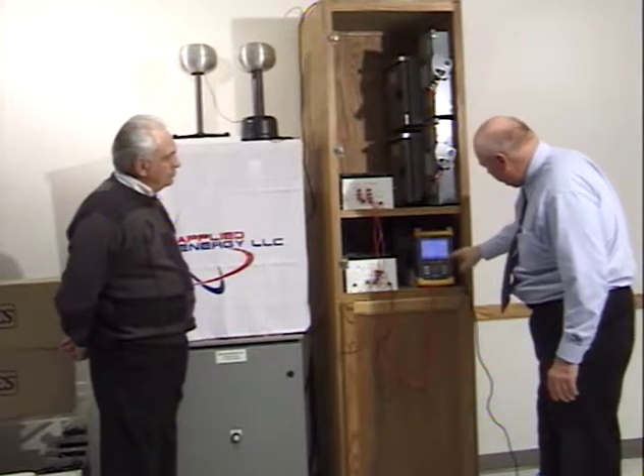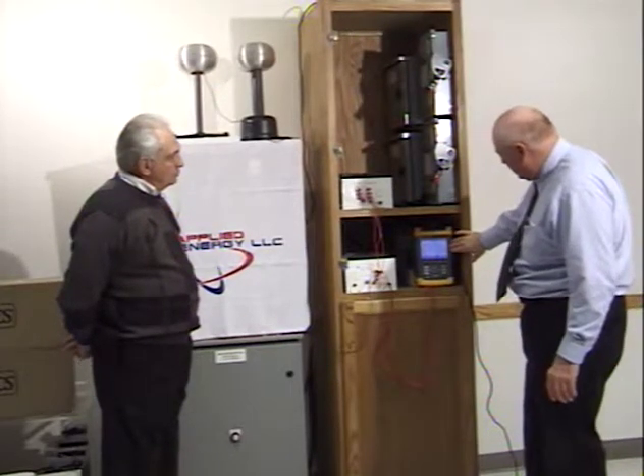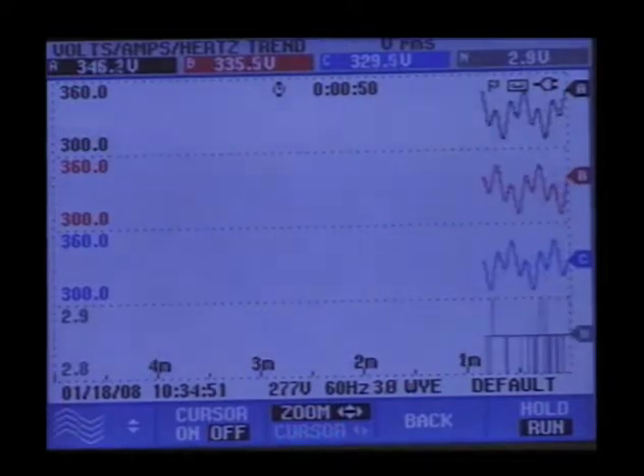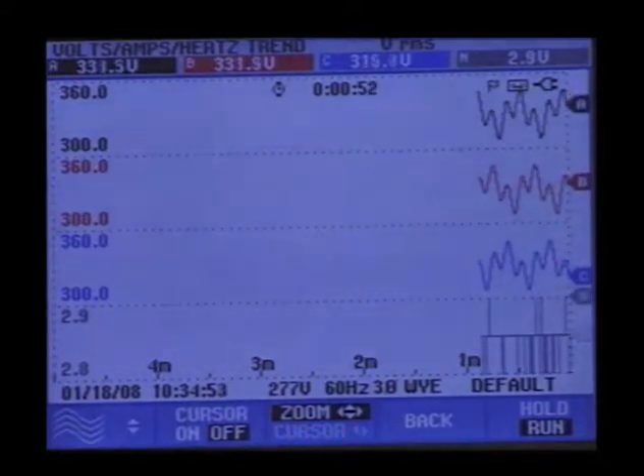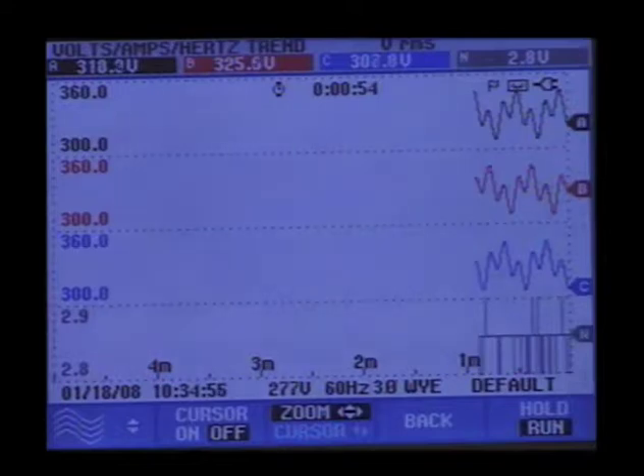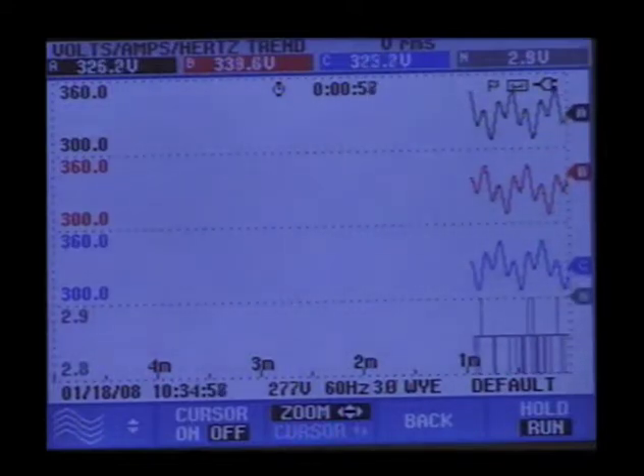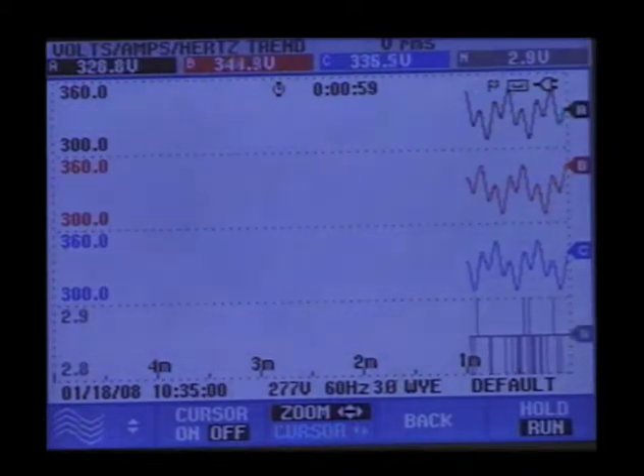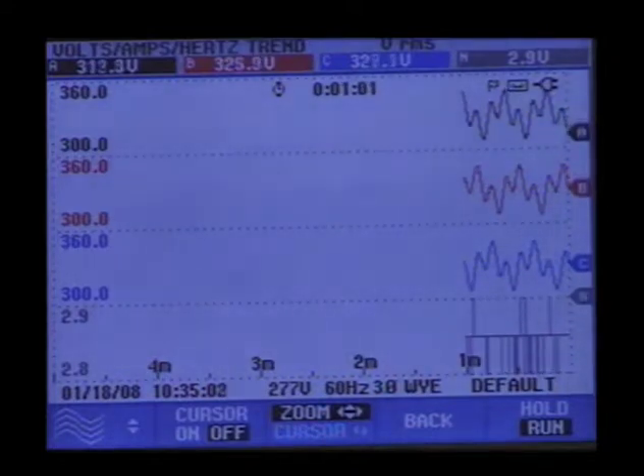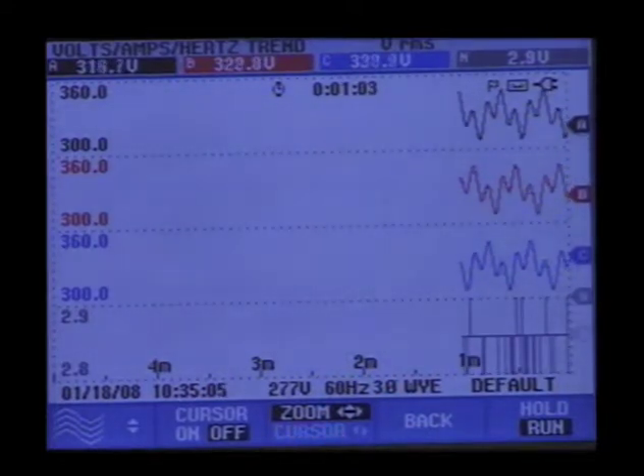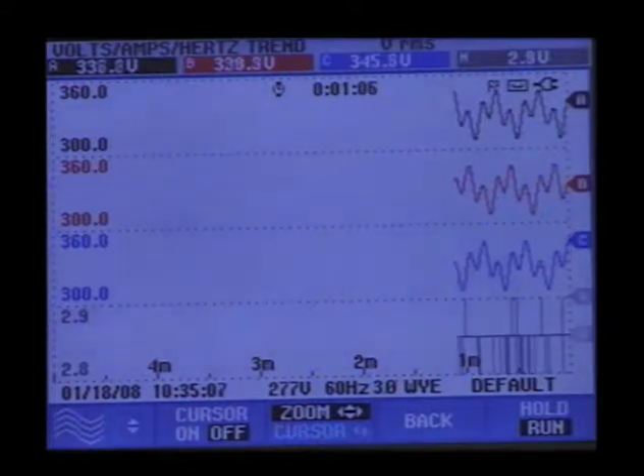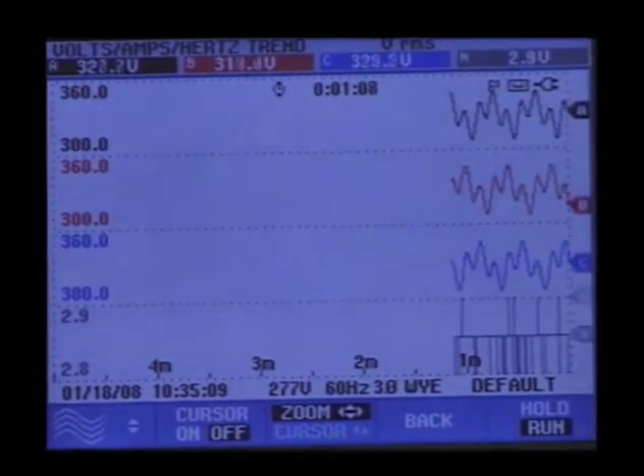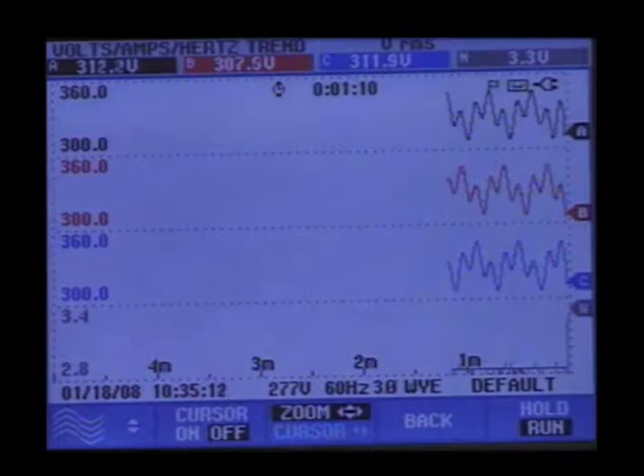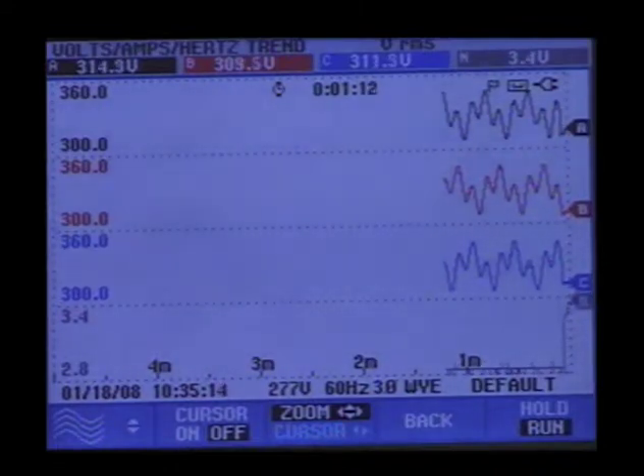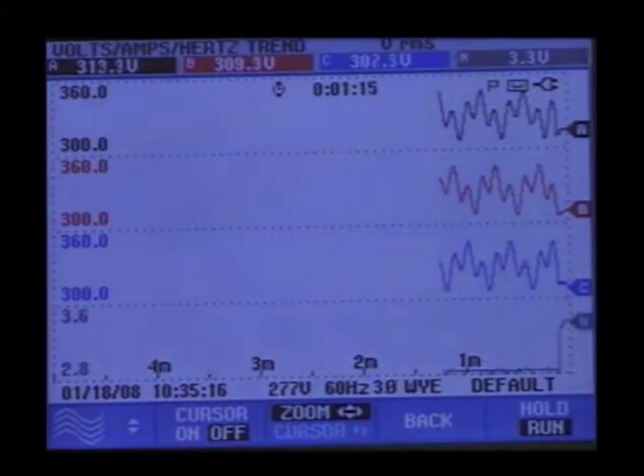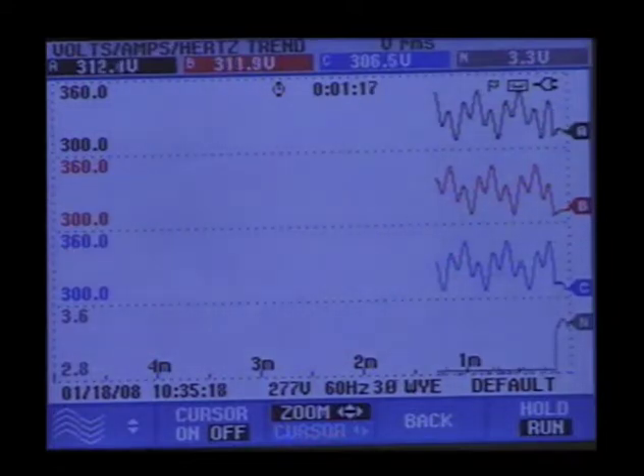We have our 3 phases of voltage, and they will vary all over the place and not be the same as each other. We have 325 volts, 307, and 319, 320. And as we vary this over time, we'll see it does have a significant swing. Voltage imbalance causes heat in a motor. Harmonic distortion causes heat in a motor. Spikes will blow little holes in the insulation, shortening the life of the insulation.